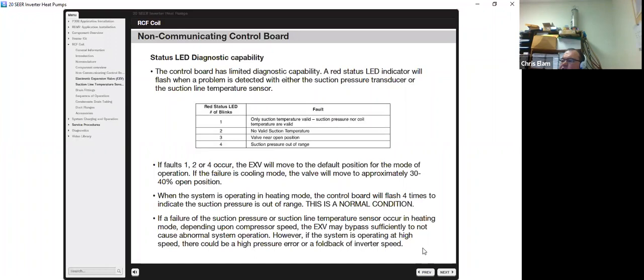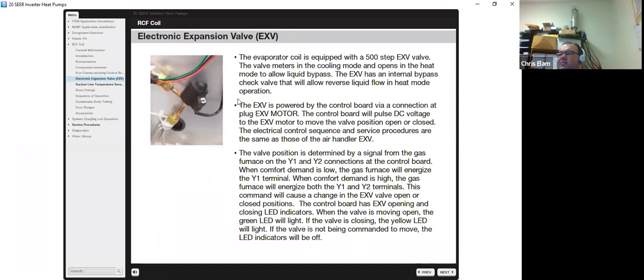If a failure of the suction pressure or suction line temperature sensor occurs in heating, depending on the compressor speed, the EXV may bypass sufficiently not to cause abnormal system damage. However, if the system is operating at high speed, there could be a high pressure error or pullback of the inverter, where your inverter starts to actually slow down. Once again, this is your EEV, same EEV. In this case here, since it's totally non-communicating, it's looking for the inputs from the sensor, the transducer, and then also the Y1 and Y2 signal to help determine what position it should go into.